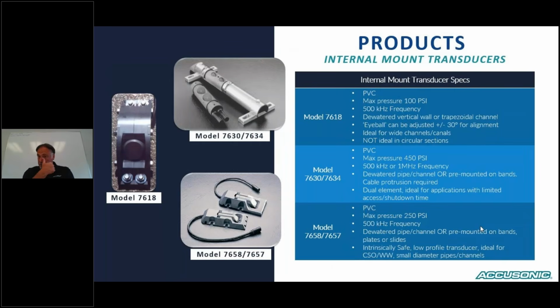For applications that do not have external access to the exterior of the pipe, we have internally mounted transducers. So for those penstocks that are encased in concrete, we have three main models that we use. The 7618, which we call our eyeball transducer, is designed and well suited for low head intakes, where you have convergent pipe sections and non-uniform pipes and channels. Our model 7634 transducer is another popular one.